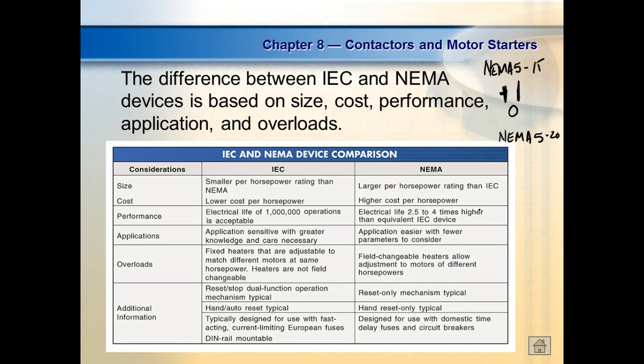So you can see IEC, since it came out of NEMA, has stricter standards. So your IEC ratings are smaller per horsepower rating than NEMA. NEMA is larger per horsepower rating than IEC. Lower cost per horsepower, higher cost per horsepower, you can actually see the difference between the two. Like I said, I tried to find the IEC charts for you. IEC, we don't use on motors. Motors are not rated in horsepower. They're rated in what? Kilowatts.